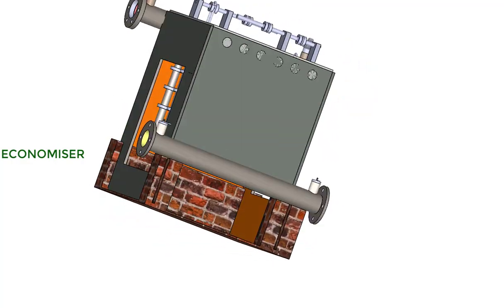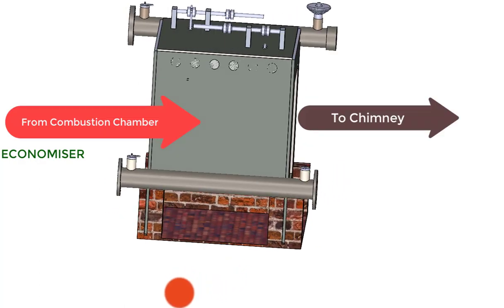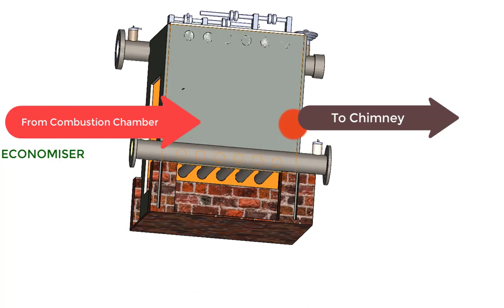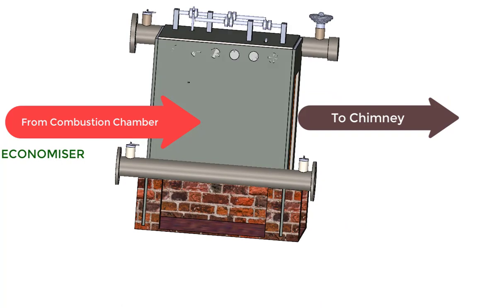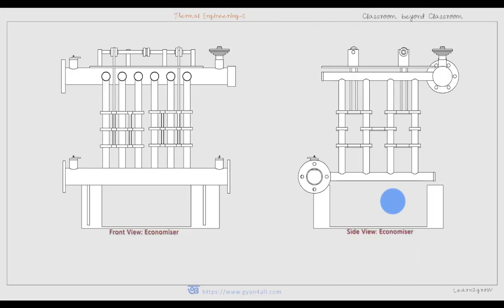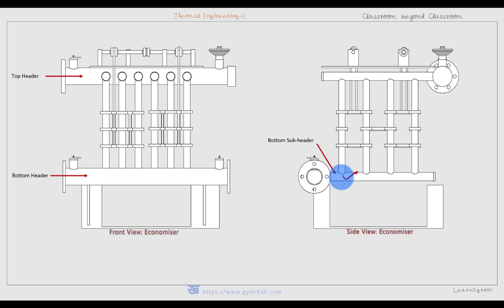This is the complete view of the Green's economizer. One door is connected toward the combustion chamber side and the other toward the chimney side, so the hot gases move from the combustion chamber to the chimney and heat the water inside the vertical tubes. Looking at the diagram: the Green's economizer consists of a group of vertical cast iron tubes. Feed water enters the bottom header, moves up to the top header, and these horizontal tubes — the bottom sub-headers — are connected to the main bottom header.